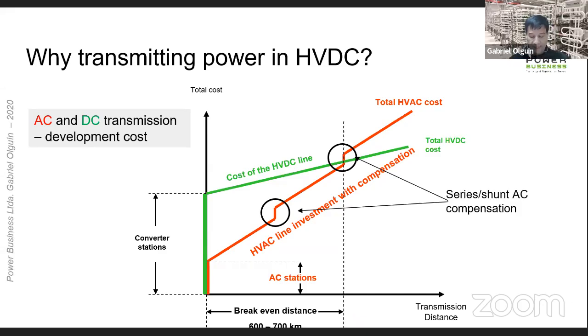of the HVAC system. The break-even distance depends on many factors, but typically varies between 600 kilometers and 700 kilometers for overhead transmission line. For insulated cable, it's much shorter, and it might be between 60 and 70 kilometers due to the need to compensate AC cables.